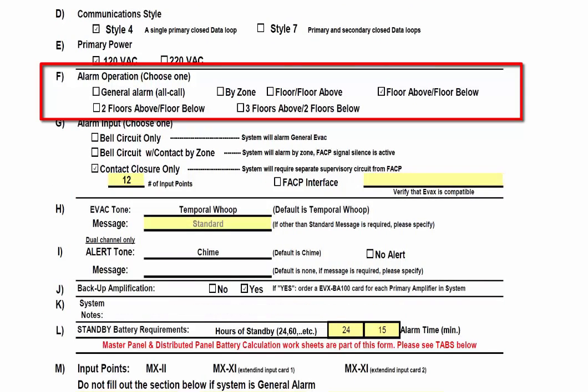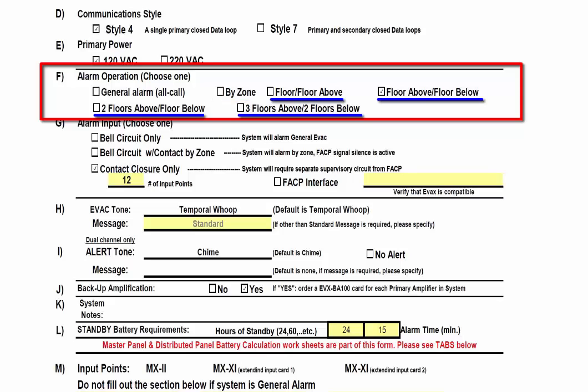Alarm operation defines how the system should operate in an alarm condition. General alarm means that all speaker circuits or zones will activate simultaneously. By zone selection indicates that the fire alarm panel will provide contact closures to the control specifying which speaker circuit should activate. The remaining options are selected when speaker circuits of specific floors should activate. For example, floor above and floor below means that the floor where the alarm occurred, the floor above, and the floor below are the only floors that should sound the evacuation message. Only one mode of alarm operation should be selected.